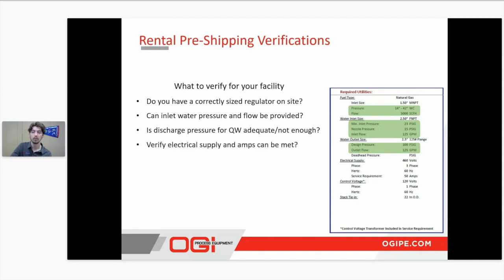And lastly, you can verify the electrical supply and amperage can be met, as I mentioned earlier. This unit is going to be 460 volts, your standard three-phase 60 hertz, and the service requirement for this one is going to be 50 amps. And then one last important thing to note is how we are going to unload it. For these containerized units, there are going to be forklift pockets on them. You just want to make sure that you have a properly sized forklift to lift these off the truck once they arrive at your facility and place them down where you'll have them placed.